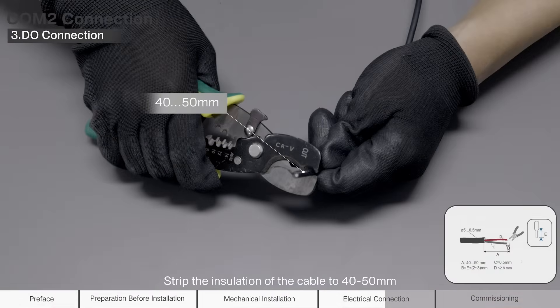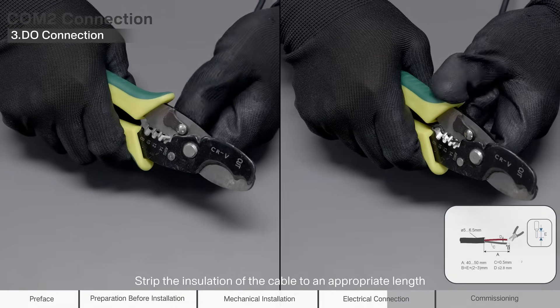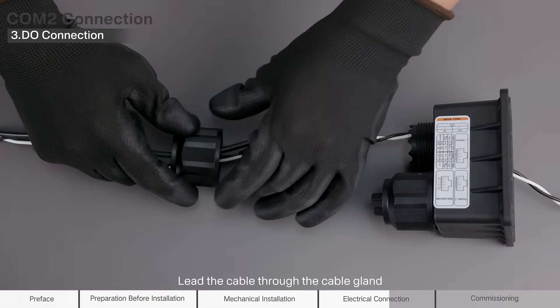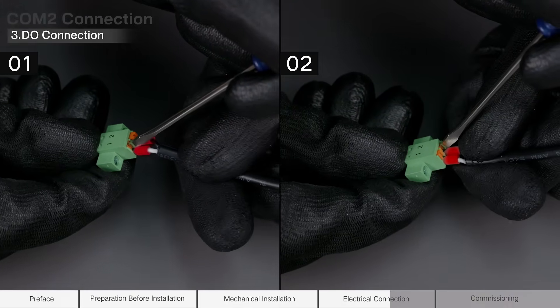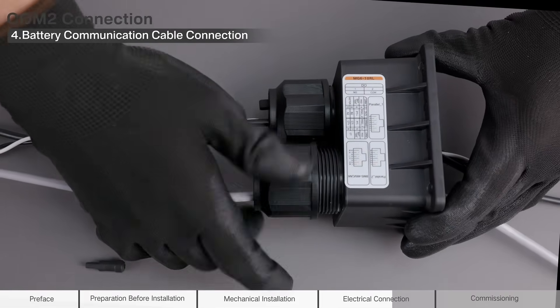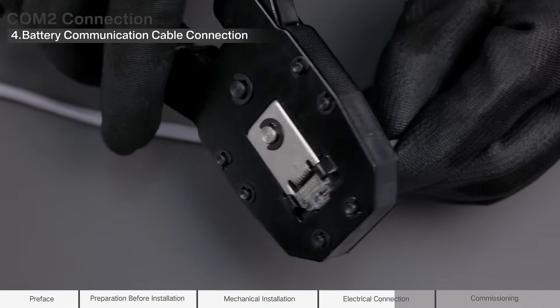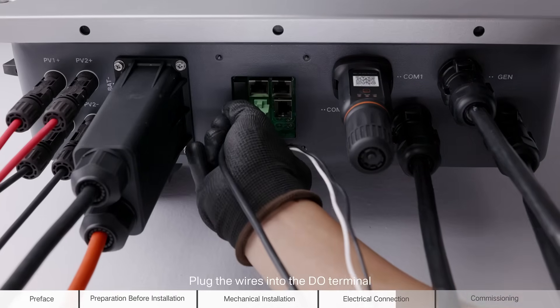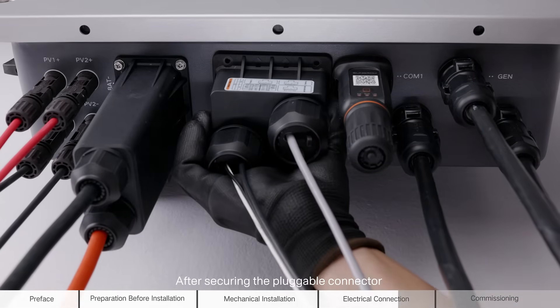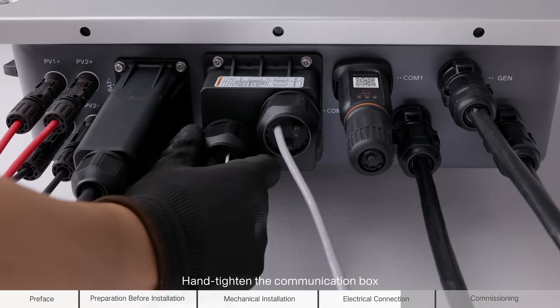Strip the insulation of the cable to 40–50 mm. Strip the insulation of the cable to an appropriate length. Lead the cable through the cable gland. Remove the seal and lead the cable through the cable gland. Make network cable crystal heads. Plug the wires into the DO terminal of the COM2 terminal. Plug the wires into the BMS485 CAN terminal of the COM2 terminal. After securing the pluggable connector to the bottom of the inverter, secure and hand tighten the communication box.